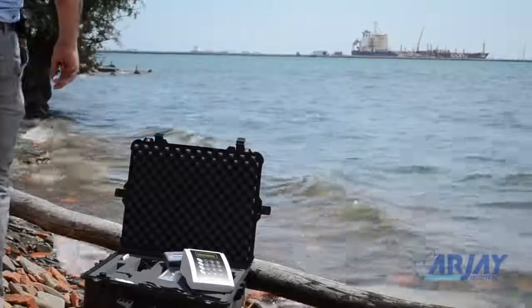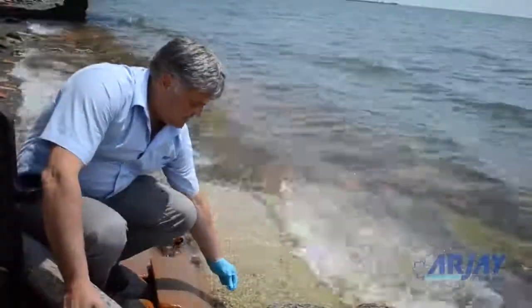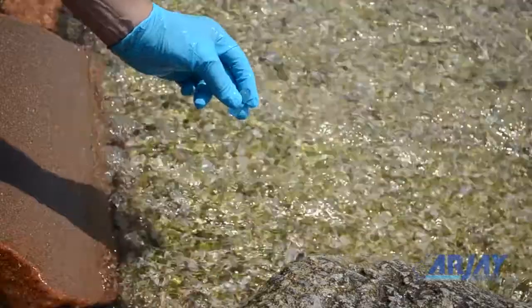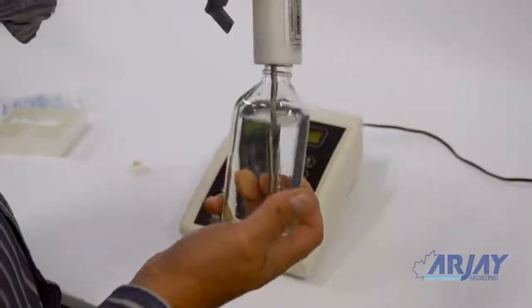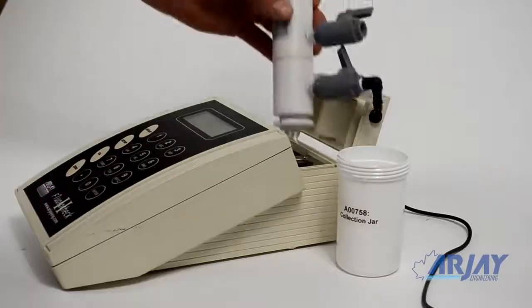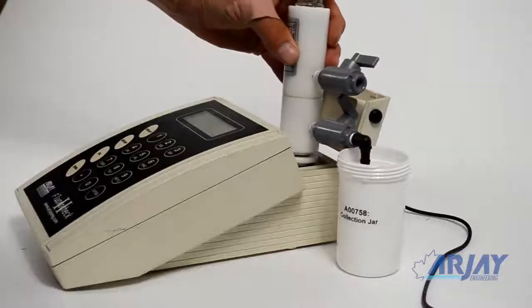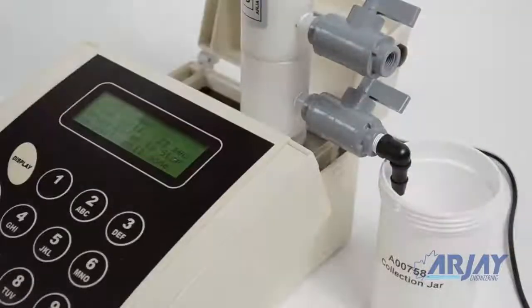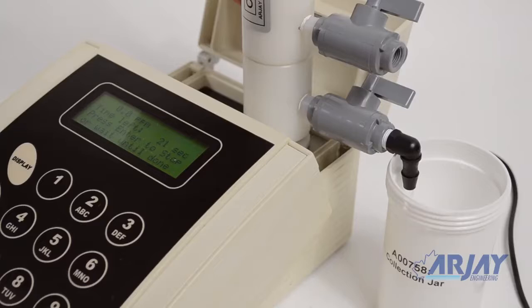A straight water sample will screen a sample for possible hydrocarbon presence. A streamed water sample will enhance the straight water test to provide more accurate results. By streaming a larger composite sample, it can provide a greater representation of your process conditions. As the sample streams through the FluoroCheck, multiple readings are taken and an average of the results is presented.